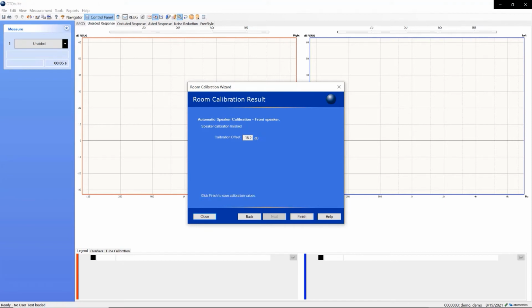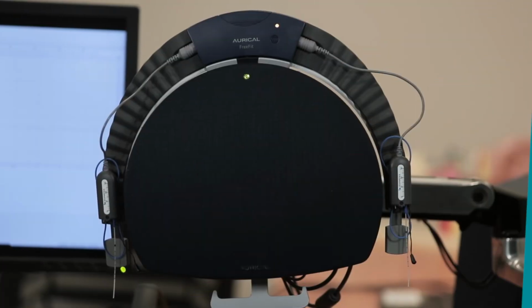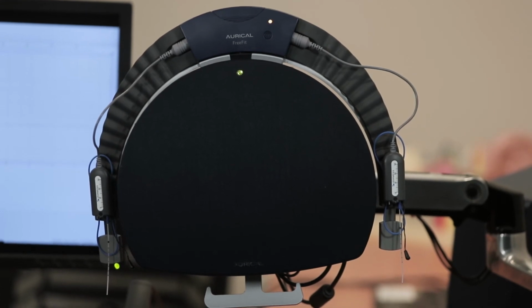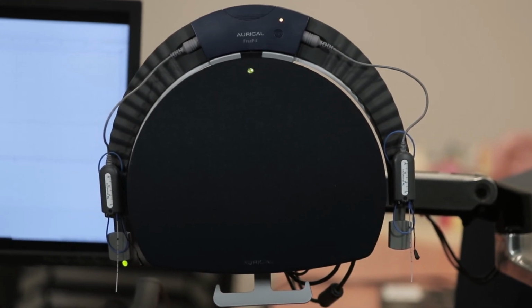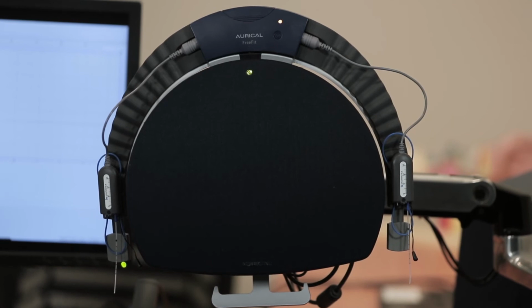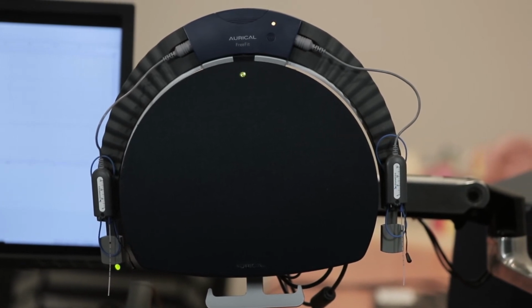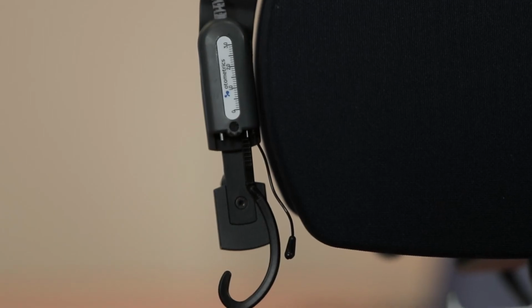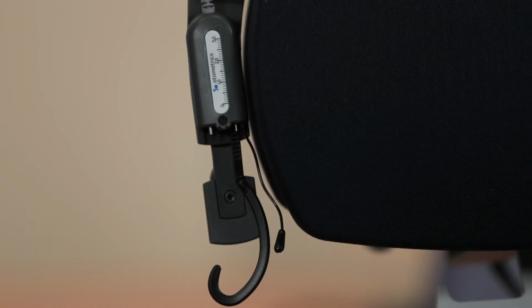When room calibration is complete, the software will indicate Speaker Calibration Finished. The calibration values that appear on your screen will vary depending upon the acoustic characteristics of your fitting room. The other calibration that is required is to complete a probe tube calibration. This must be completed before the first time you use your Aurical PMM system, but it is recommended to perform probe tube calibration every time you connect a new probe tube.